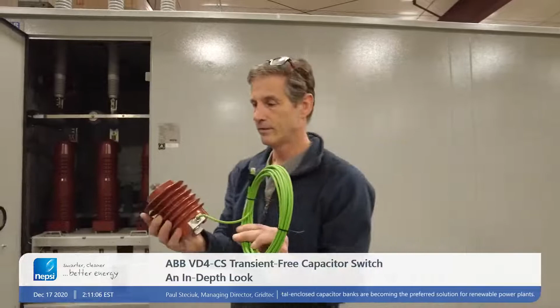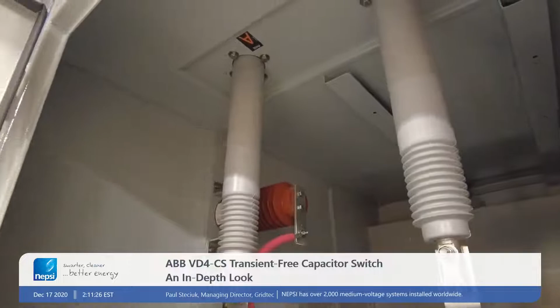So maybe you can talk a little about the voltage sensor here, its location, phase rotation, things like that. This is a voltage sensor, a low voltage sensor, a 15 kV sensor, basically the same sensor as the one located internal to the capacitor bank. The sensor always has to go on the left pole, normally A phase for us, and it has to connect on the line side of the switch on A phase, at the first pole on the left.